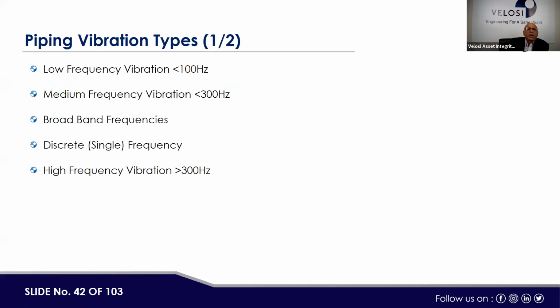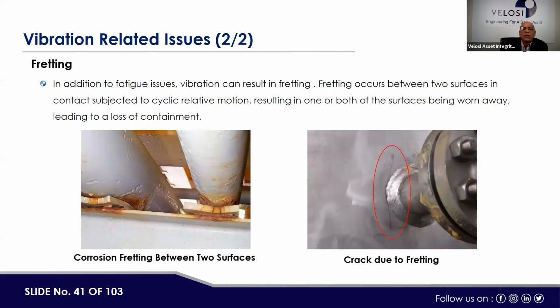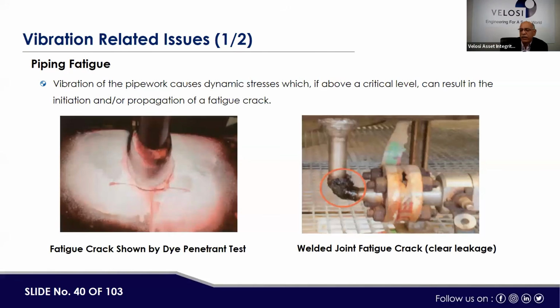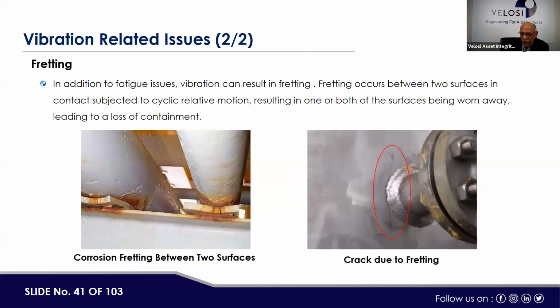But let us try to understand what we have understood up to now: what vibration is, and what kind of causes can lead to high vibration. Number two, if these vibrations are there, what could be the next consequence? The consequence is high corrosion and failure, right? So it is a serious issue, and we need to maintain proper integrity of the piping system. That's why vibrations always need to be kept under control.